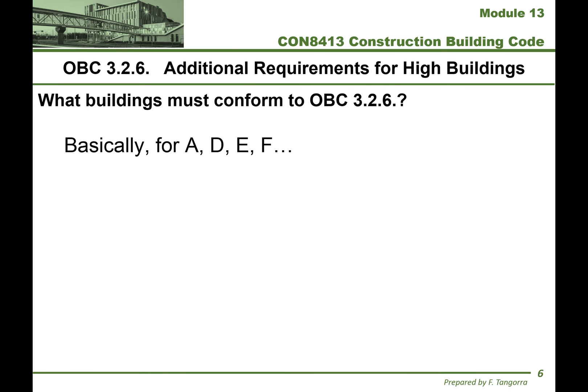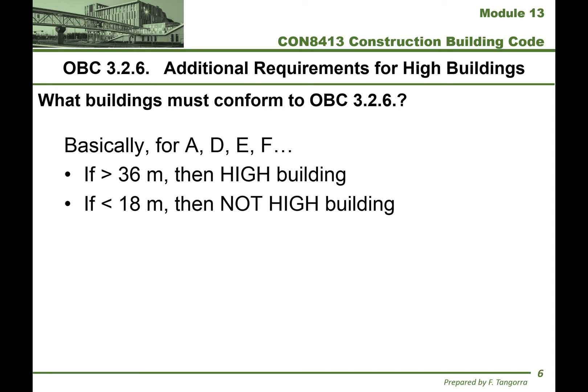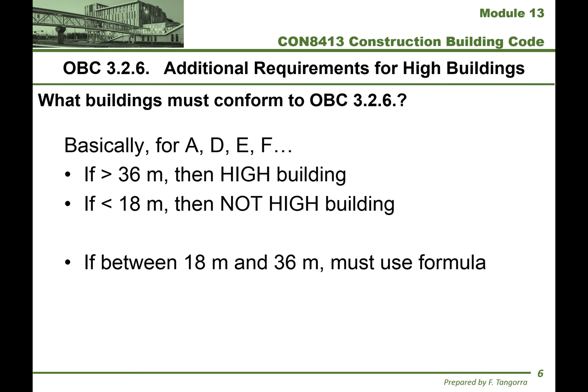For occupancies A — so that's all A's — D, E, and all F's: if your building is more than 36 meters high, it's considered a high building under 3.2.6. If your building is less than 18 meters, it's not a high building. But if it's between 18 and 36 meters, you must use a specific formula that's written out in words in the building code, which we will go over as part of this lecture.